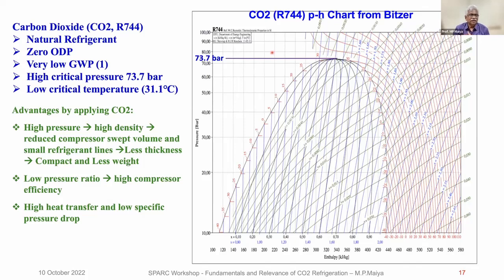High pressure means high gas density, so reduced compressor swept volume, because the compressor becomes small. Refrigerant lines and tubes have very small diameter and less thickness is sufficient, so it is compact and light. Ultimately, the whole system becomes compact and lighter compared to conventional refrigerants. The pressure ratio is low, so compressor efficiency is high. Heat transfer properties are good: low viscosity and high thermal conductivity. So you get a high heat transfer rate and low pressure drop, because of low viscosity. These are advantages, but the critical temperature is low, so you have to go for a transcritical cycle.